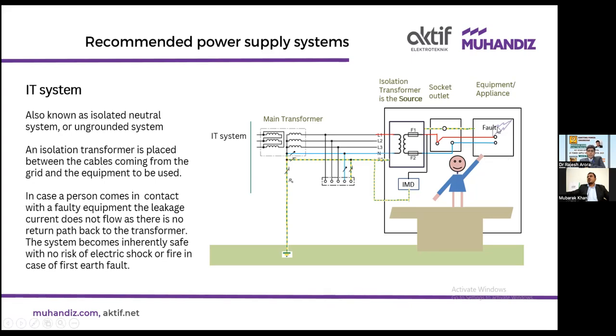This particular, so there will not be any leakage current and it will display the resistance of the phase with respect to ground. And if the resistance is low, we say that there is an earth fault. So in this way, without tripping the system, only through monitoring the resistance, we are able to say that there is an earth fault. Okay, thus this makes a safer power supply system for operation theaters.